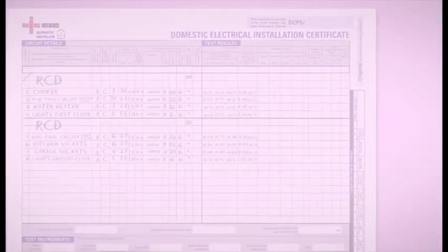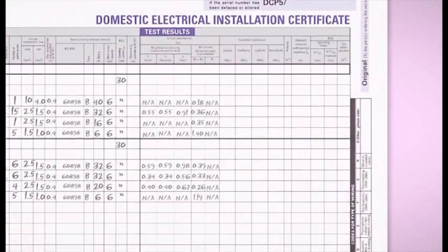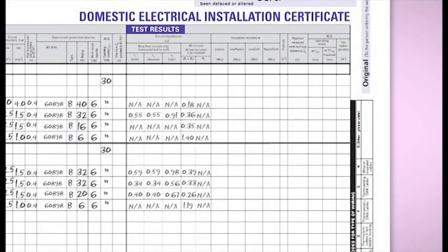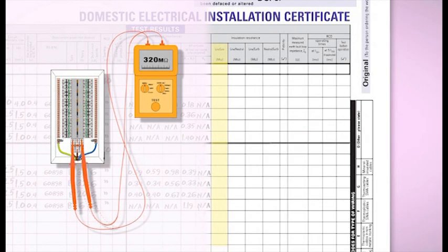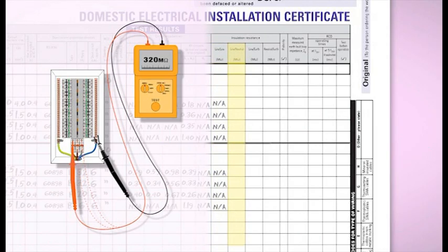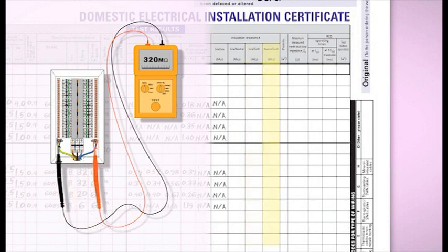The next four columns are for the results of insulation resistance tests. The first column, line-to-line resistance, is for a three-phase circuit where tests are undertaken between each phase of the supply. The lowest value of resistance measured should be written in the box, or not applicable if the installation is single-phase. Then we have line and neutral. Again, for three-phase, you would have to test between each line conductor and neutral and record the lowest value. And repeat again for the next column, line and earth. Finally, there is neutral and earth.